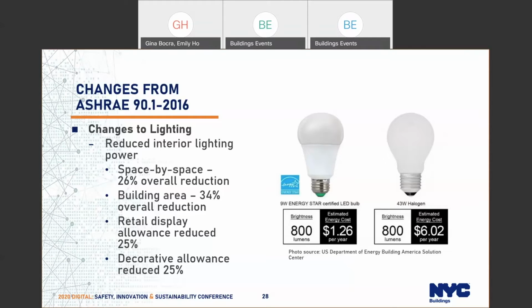Additionally, there's a retail display allowance that reduced by 25%. I think that allowance hadn't changed in many code cycles. And then the decorative lighting allowance also reduced by 25%. So this is just the code catching up with the LED market that's now prevalent and cost effective. That's why we're seeing these major lighting changes. It's really just the code catching up with the market.